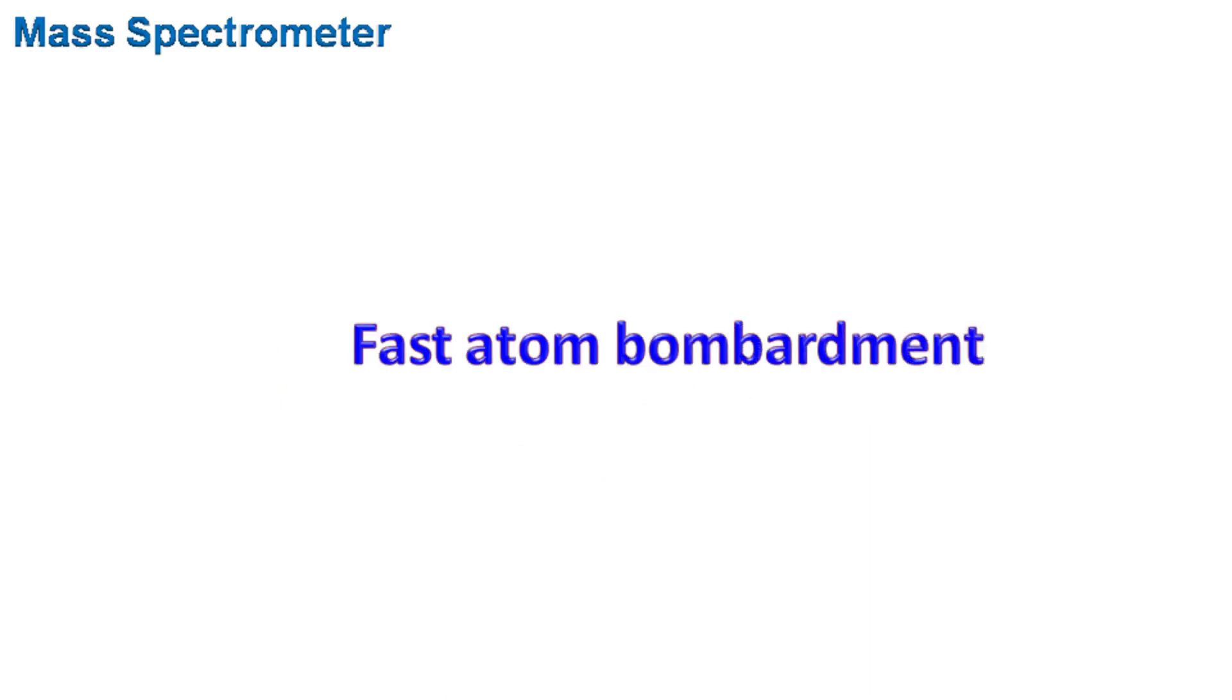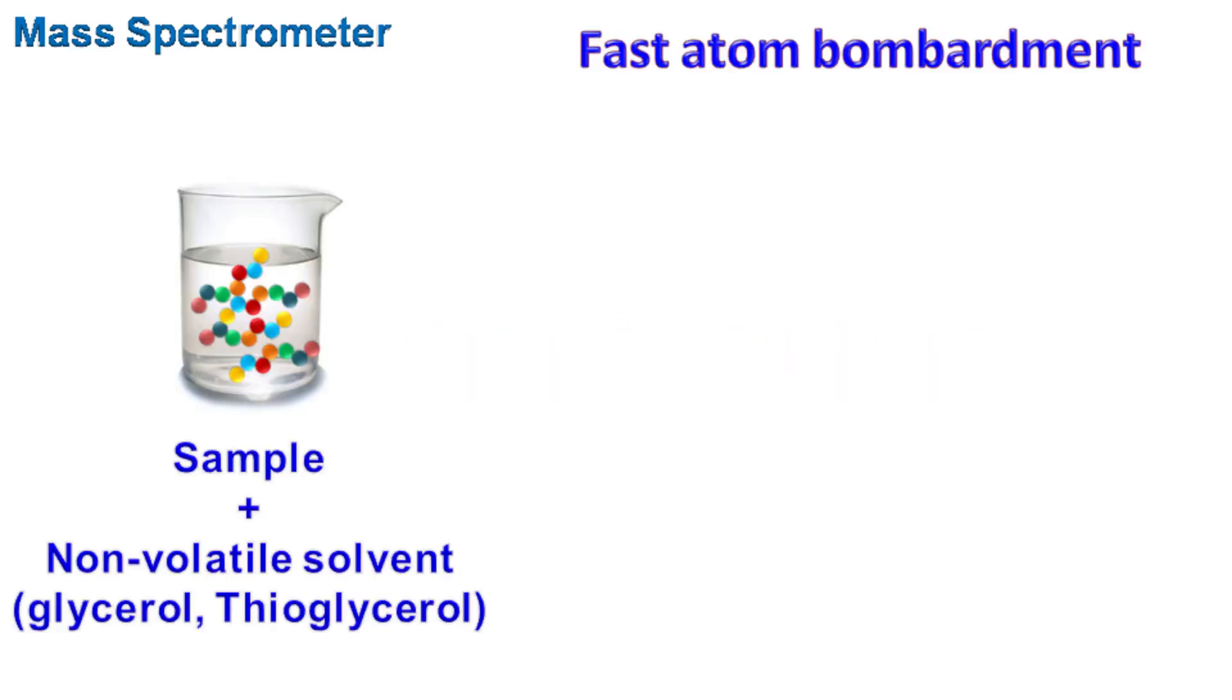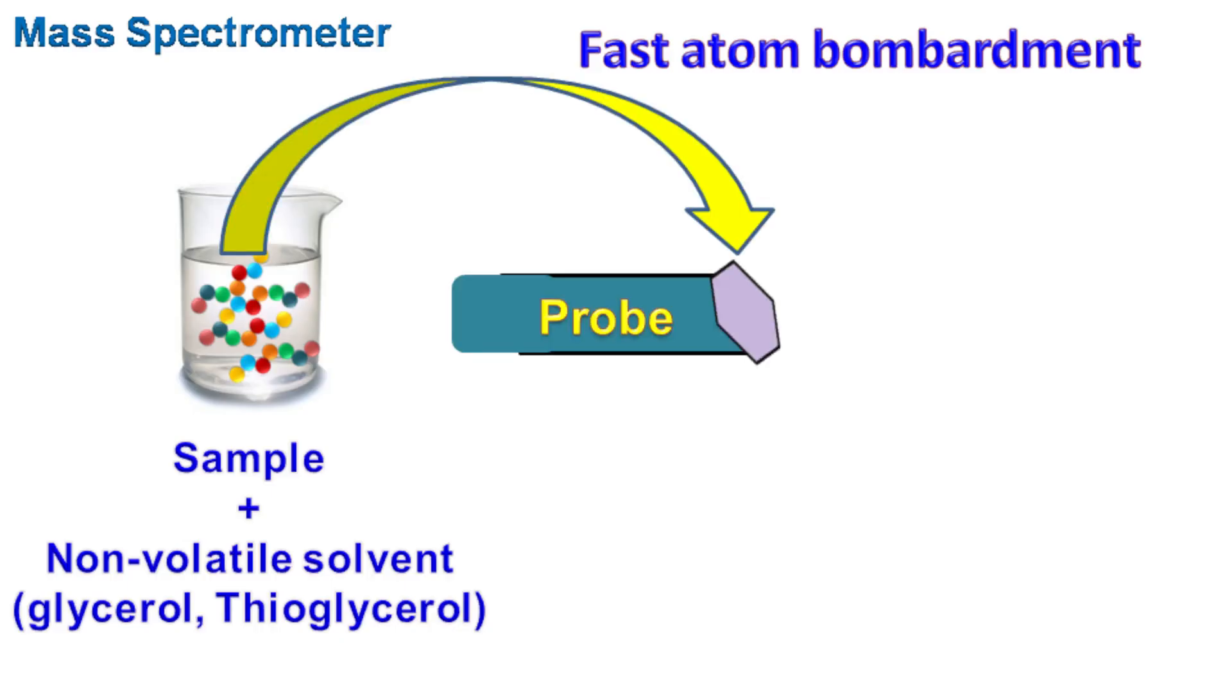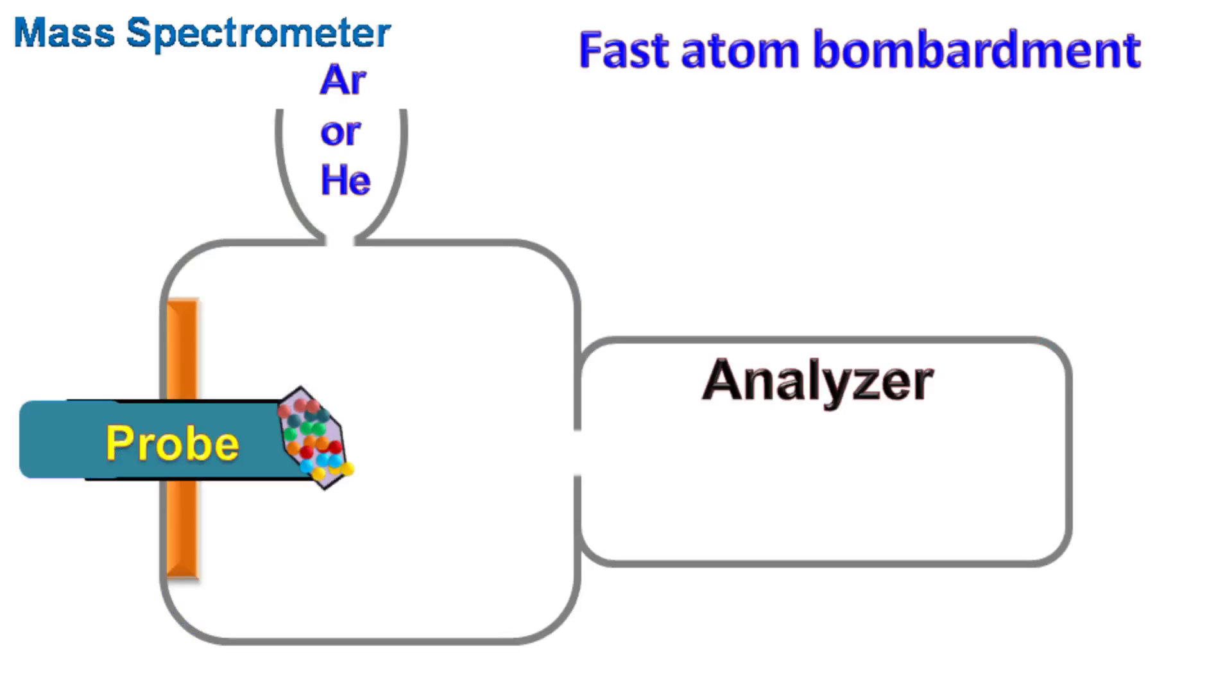Fast atom bombardment: In this technique, the sample molecules are mixed with involatile solvents such as glycerol or thioglycerol. This mixture is applied on the probe and bombarded with a beam of inert gas such as argon, helium, or xenon at high velocity. This bombardment ionizes the sample molecules which are to be analyzed.